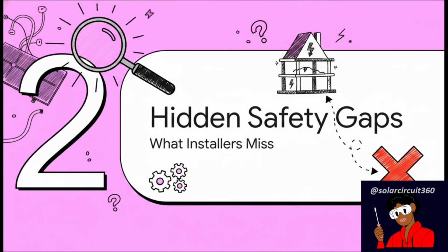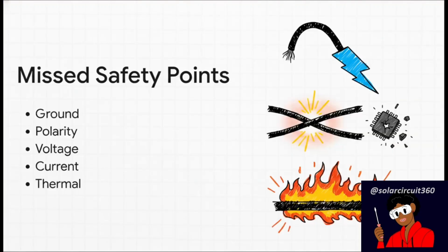Moving on to Section 2, Hidden Safety Gaps, What Installers Miss. This is where that amateur startup sequence totally falls apart, and the high-stakes detective work really begins. Our sources point out several critical safety points that so often go completely unverified. For example, installers might connect the grounding conductors, right? But they never actually test for earth-ground continuity. Missing that step creates an immediate, potentially fatal shock hazard.